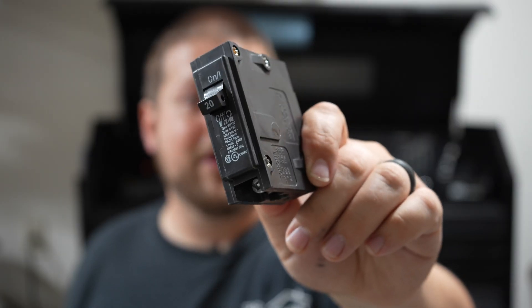When either of these devices trip during normal use, it's really tempting to just hit the reset button to get everything working again, but you should also hit the test button one more time to make sure the protection is still intact. It's also recommended to replace GFCI and AFCI protection every 15 to 20 years, compared to normal breakers which should be replaced every 30 to 40 years.